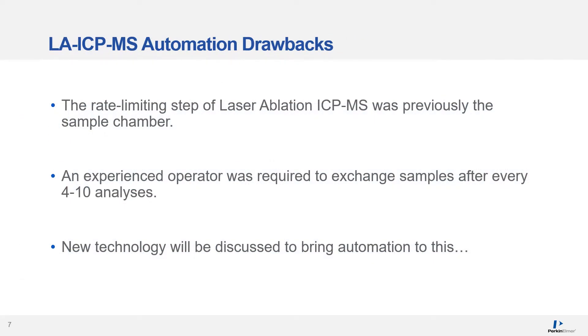Looking at some of the current drawbacks in the automation of laser ablation ICP-MS, the rate-limiting step was previously the sample chamber. Sample chambers used in laser ablation ICP-MS can typically fit about five samples, maybe ten, and an experienced operator was required to exchange samples every four to ten analyses. However, we will discuss new technology and how we can automate this.